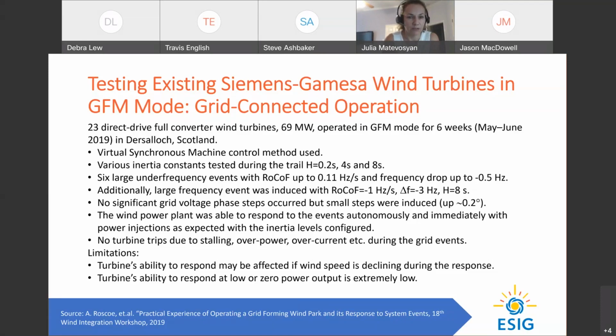One thing I forgot to mention is that they were using the rotational energy of wind turbines as an energy buffer to tap into when they needed to provide active power injection during frequency events, providing this type of virtual inertial response. Obviously, because of that, the turbine's ability to respond is affected by wind speed. They encountered several events where wind speed was declining at the time of the response, and that deteriorated the virtual inertial response from wind turbines. Also, the wind turbine's ability to respond at low or zero power output is extremely low. These limitations can be overcome by having small batteries at the site to provide this response in the inertial time frame.